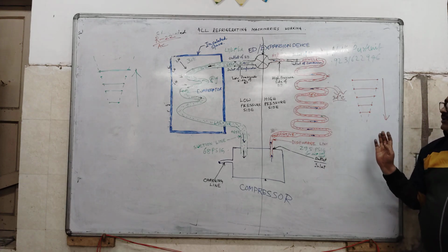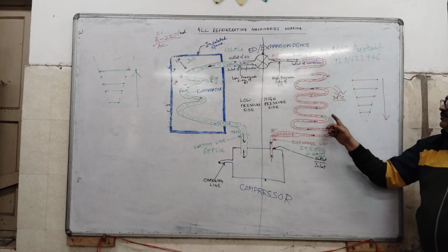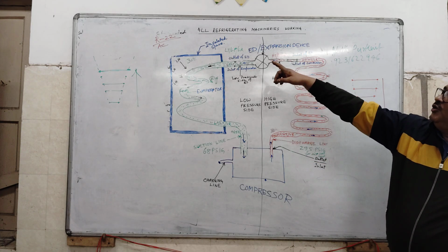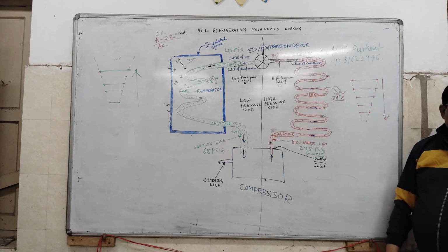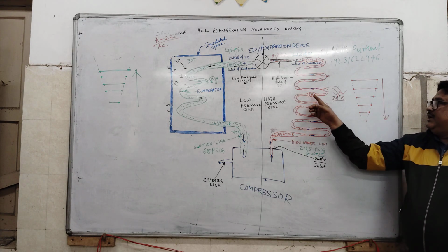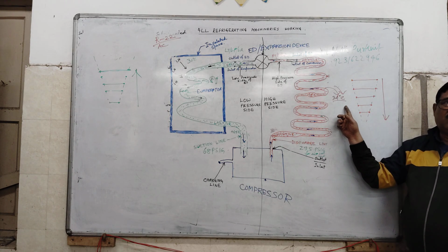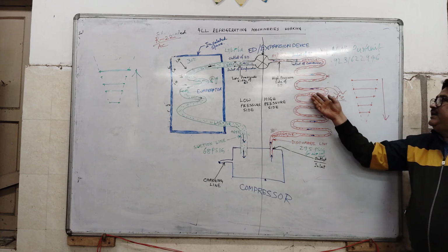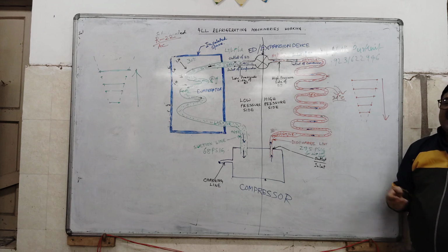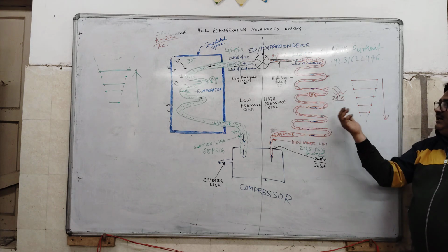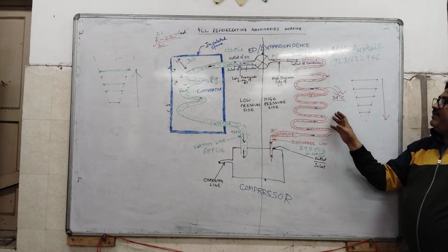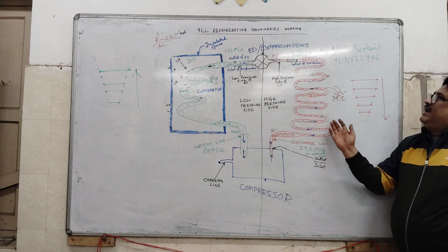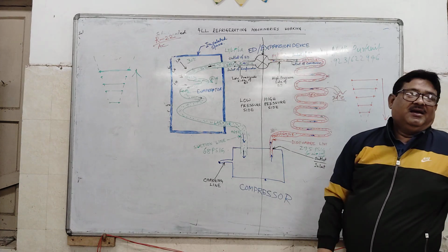So the temperature inside becomes about 54 degrees Celsius due to the pressure. If we use an R22 AC system, it is 54 degrees Celsius, whereas the ambient temperature is taken as 34 degrees Celsius. So a 20 degree difference has come, so heat can be discarded to the atmosphere, and due to rejection of heat, that vapor refrigerant comes back to liquid and it will enter the expansion device again and again.